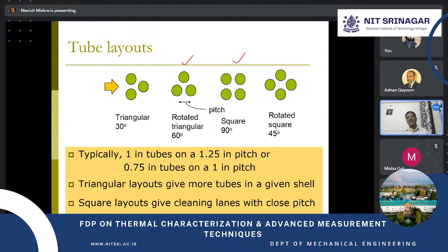As far as the tube side is concerned, how do you calculate hydraulic diameter? Hydraulic diameter for the tube side, if I substitute 4A by P, where A is free flow area and P is wetted perimeter — coincidentally, or fortunately, this comes out to be the hydraulic diameter or the nominal diameter. But when it is the shell side, the case is not that simple.